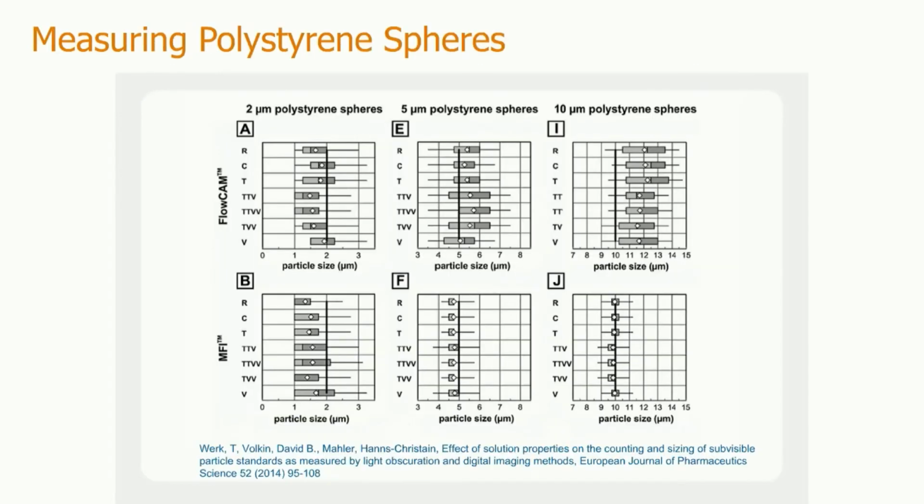This slide shows a comparison of MFI and another fluid imaging system, comparing the measurement of polystyrene spheres. Here you can see, particularly with the 5 and 10 micron beads, that MFI exhibits better precision and accuracy with sizing these beads.